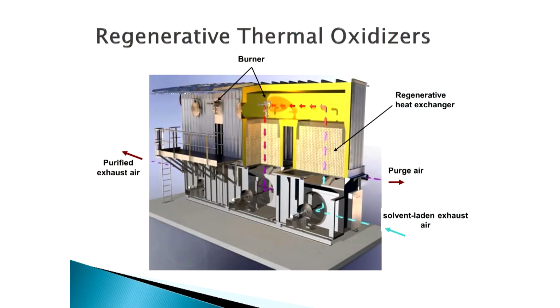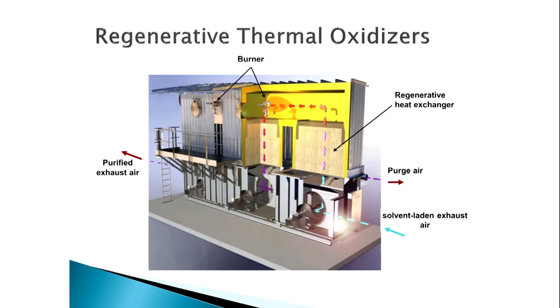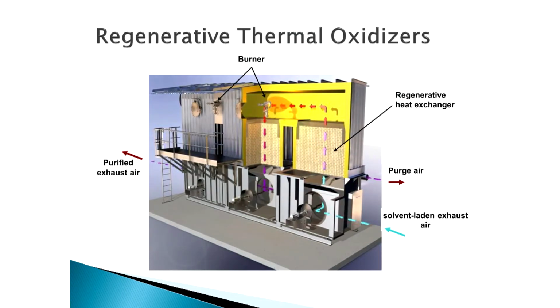This is what a common oxidizer looks like. You see a 3-tower here. If it was a 2-tower, the cutaway would just be these 2 heat exchanger columns. And so what you end up with is a number of valves, inlet and outlet valves, that direct the airflow. And you have air that comes into the inlet. The air gets preheated through the incoming heat exchanger. The VOCs combust, and there's an exothermic heat that's released. And we then capture that heat in the heat sink or the outgoing heat exchanger. And then we switch the valve direction, and the heat sink then becomes the heat source, and so on and so forth. And we keep flipping the heat back and forth between what is ultimately a ceramic mass heat storage device, and it's a little bit different than what a metal style heat exchanger ultimately is.